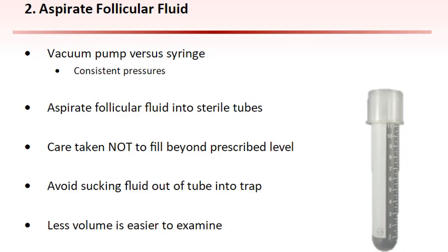The vacuum pump is an ideal way to maintain constant suction in a repeatable way from follicle to follicle and from patient to patient. The use of a vacuum pump requires that the pump undergo quality control checks to confirm the displayed vacuum pressure. In addition, the vacuum pressure displayed during the retrieval should be checked frequently to assure that it does not deviate from predetermined values. The use of a syringe, while less expensive in the short run, may be less regulated and less consistent from follicle to follicle and patient to patient. High suction pressures may affect outcome.